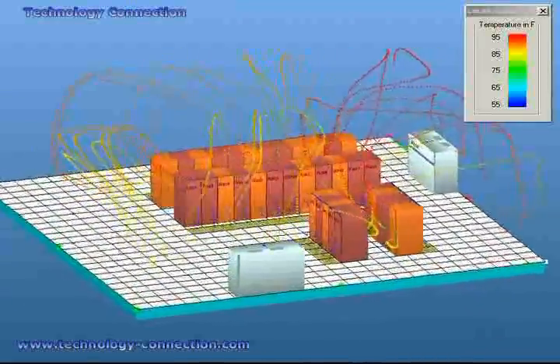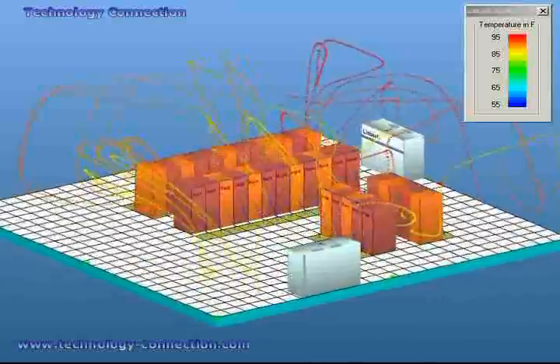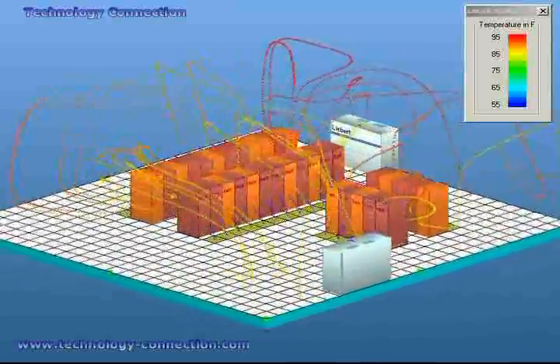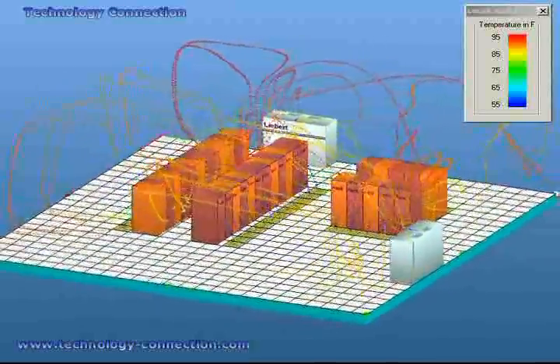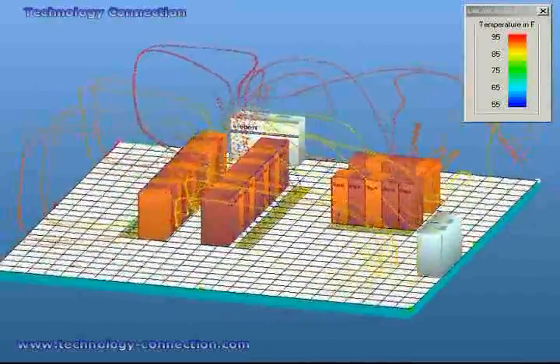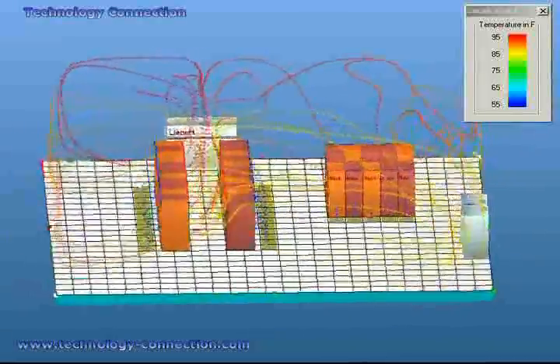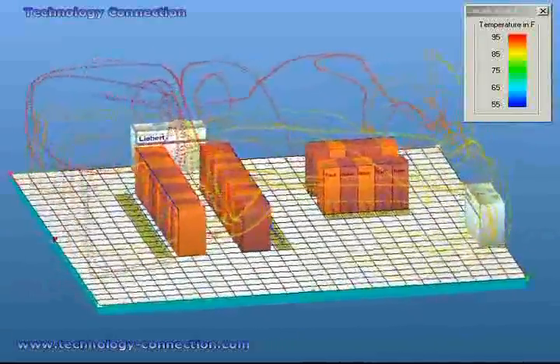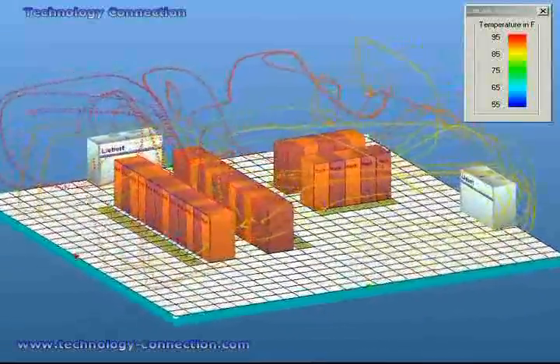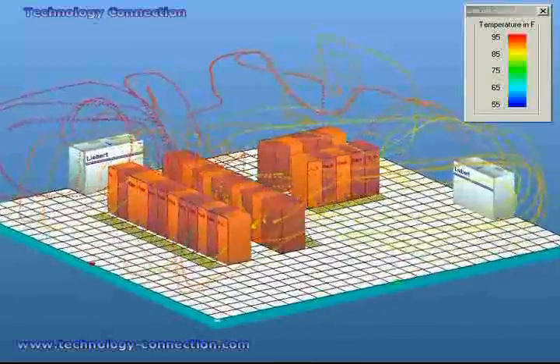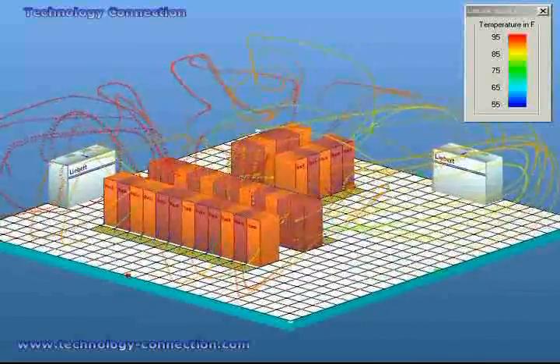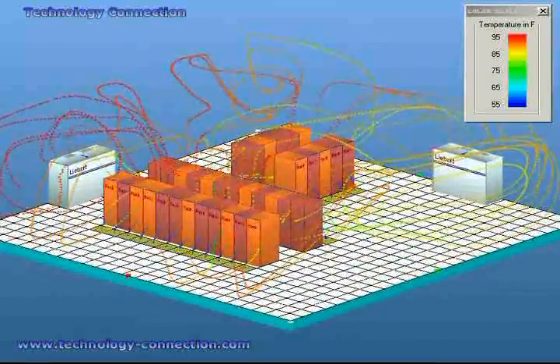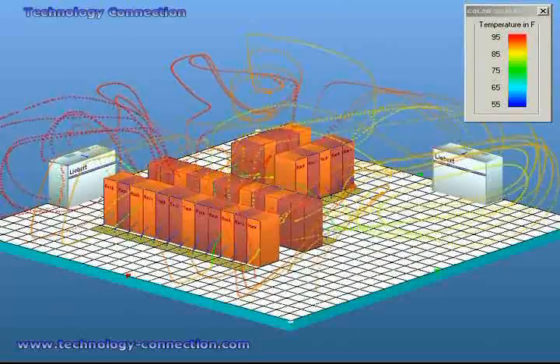By using CFD modeling, we can apply tangible characteristics to the airflow within your data center. In this demonstration, you will notice simulated air releasing from the perforated tiles and hitting the heat load. This simulation allows us to document and visualize the path air will take through any given data center with great accuracy.